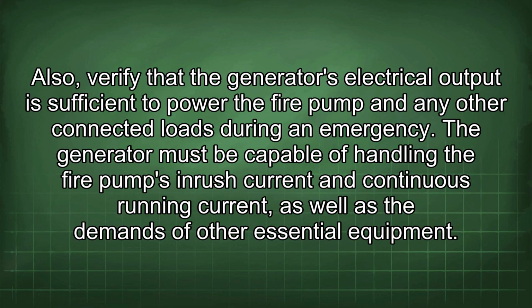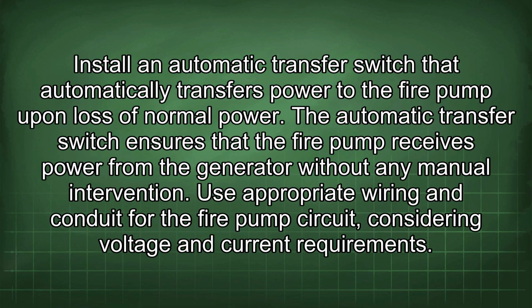Also, verify that the generator's electrical output is sufficient to power the fire pump and any other connected loads during an emergency. The generator must be capable of handling the fire pump's inrush current and continuous running current, as well as the demands of other essential equipment. Install an automatic transfer switch that automatically transfers power to the fire pump upon loss of normal power. The automatic transfer switch ensures that the fire pump receives power from the generator without any manual intervention.